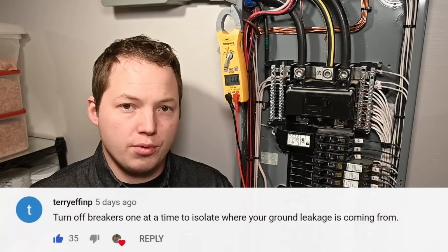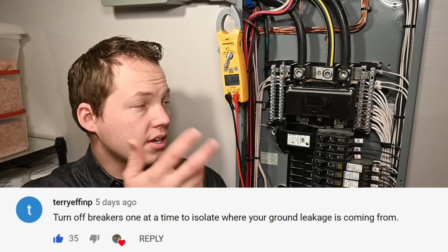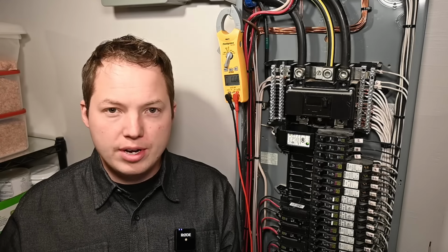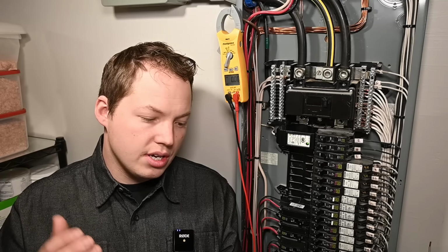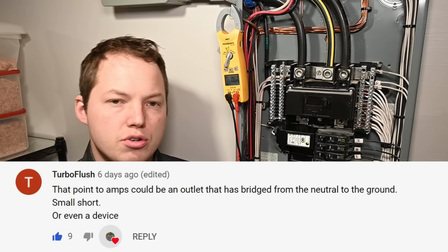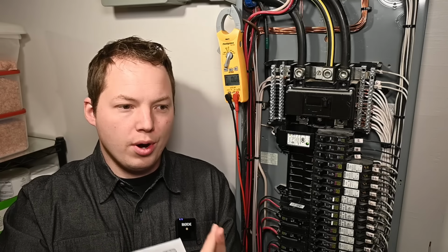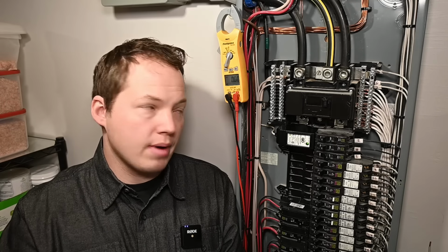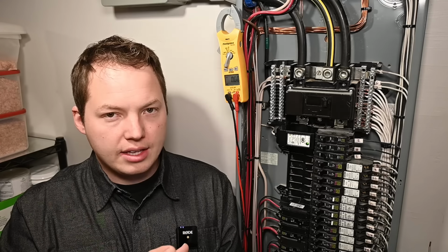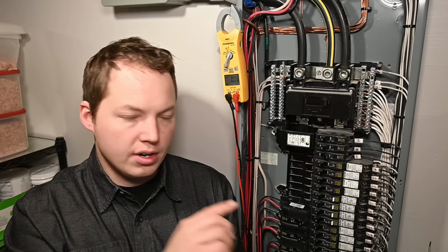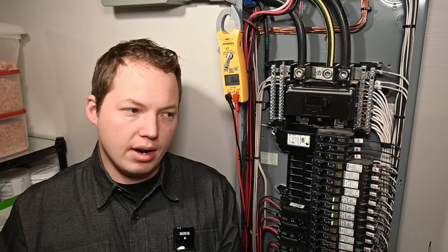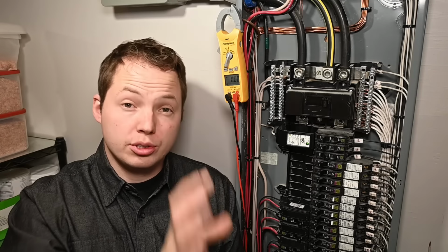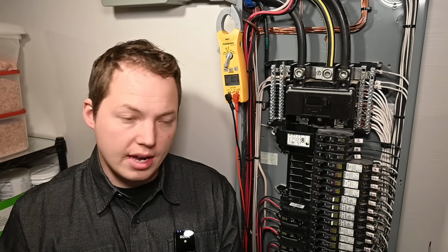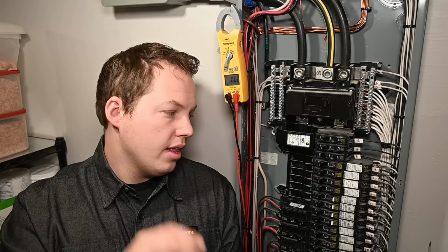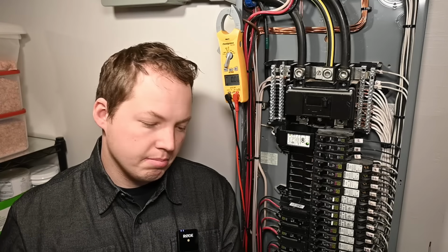One of the top comments was just to turn one breaker off at a time until we see that the current goes to zero, and then we should be able to track down which appliances could be causing the issues. Another was a bridged neutral in a box somewhere. So if we had a neutral and a ground wire that somehow were connected together in one of the electrical boxes somewhere in the house, that could cause additional current to flow to ground, and that could be what we're sensing here. Now I don't think that's very likely, because the vast majority of my breakers are arc fault or ground fault, and any arc fault or ground fault circuit breaker like what we have in here will trip if that is occurring. If there is a neutral and ground connected in a box somewhere, my breakers would be tripping, so I don't think that's likely, but it could be.